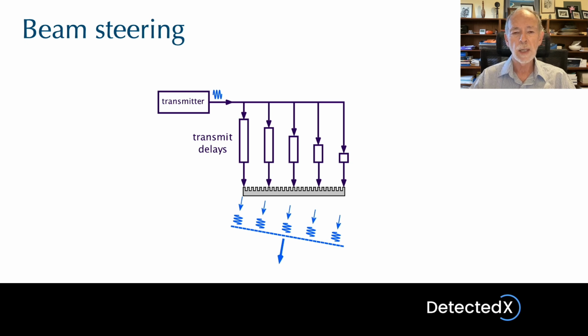Again, we have the transmitter connected via delays to the transducer, to each of the elements. You'll notice here that the delays vary in length, so that the left-hand element has the longest delay time and therefore it will transmit last. The right-hand element has the shortest delay and therefore it will transmit first. And so when we take that into account, you can see that the machine will send a beam at an angle such as I've shown in this drawing. Again, the machine can calculate the delays necessary to point the beam in any direction that is required. In reality, of course, focusing and steering of the beam are combined, and the delays are calculated to achieve both of those functions in combination.